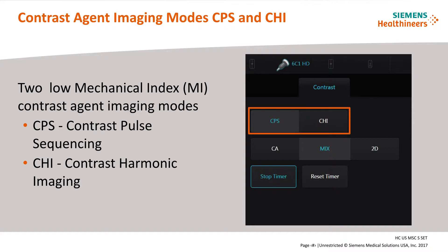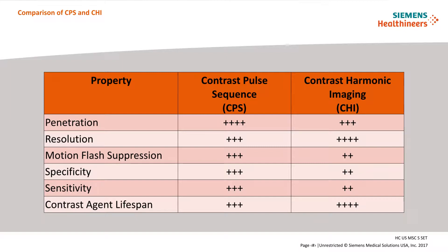Contrast harmonic imaging, or CHI, is a low mechanical index harmonic imaging technique that improves contrast image resolution and frame rate compared to fundamental imaging techniques. When deciding on an imaging technique, the user must consider the type of imaging being performed. If the region of interest is deep in the liver, CPS may be preferred over CHI due to higher penetration and higher motion flash suppression. If the region of interest is small and superficial, CHI may be preferred over CPS, as CHI has higher resolution and lower bubble destruction. The user interface allows quick switching between imaging modes with no image or scanning interruption.